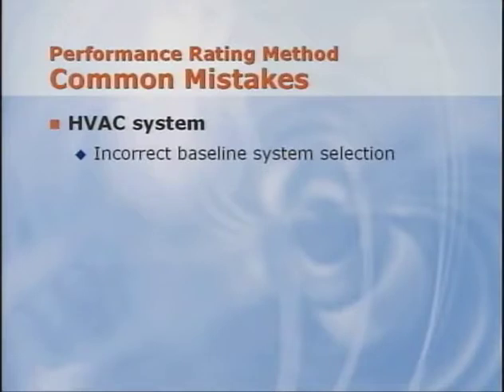The most common error is incorrectly selecting the appropriate HVAC system type for the baseline. Appendix G includes a set of tables to define which HVAC system to assume for the baseline. For small, low-rise buildings, this is often packaged rooftop air conditioners or heat pumps. For mid-rise buildings, the baseline system is a packaged rooftop VAV system, and for larger or taller buildings, the baseline is VAV with chilled water, as you saw in our previous examples.